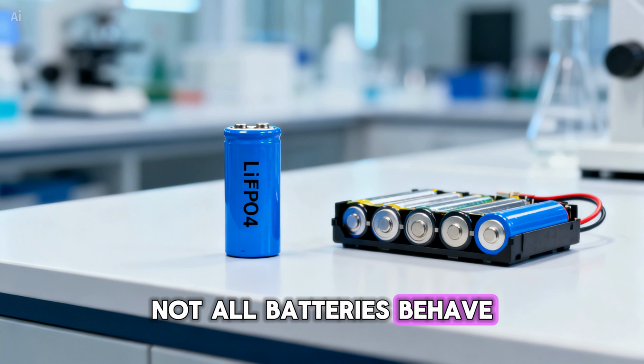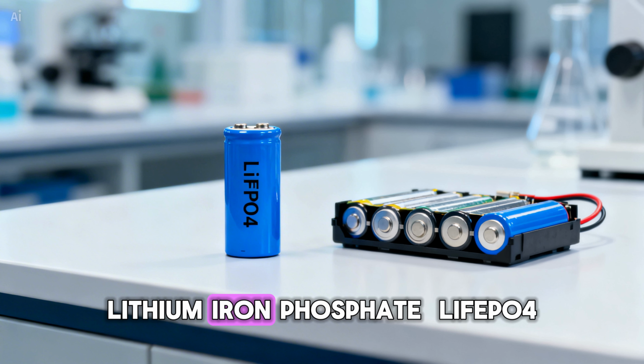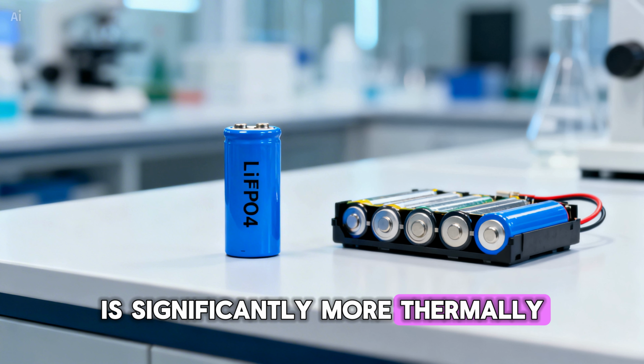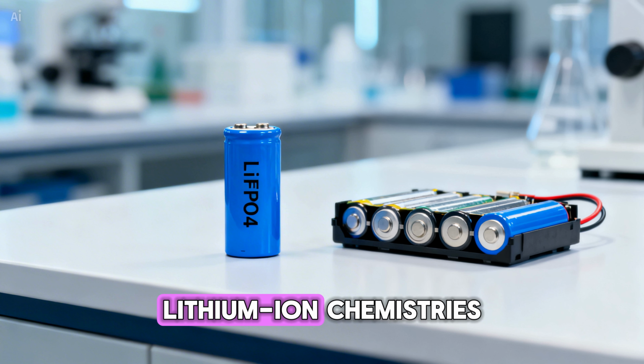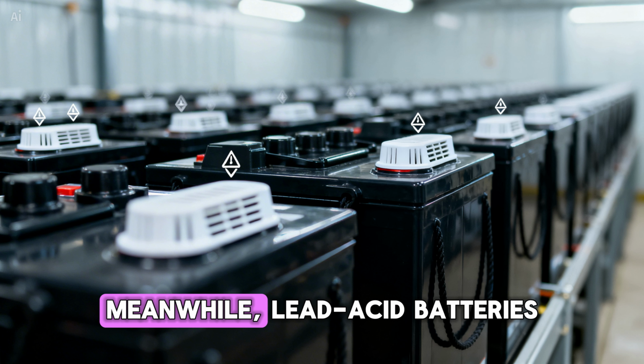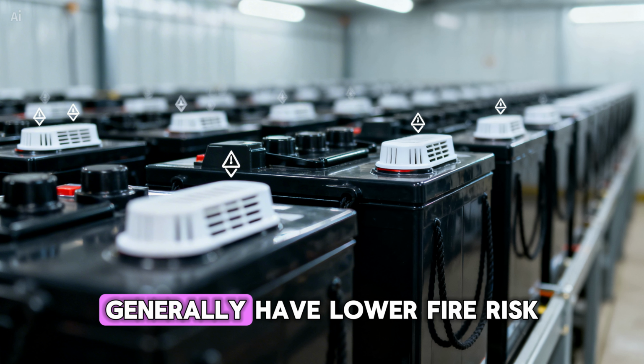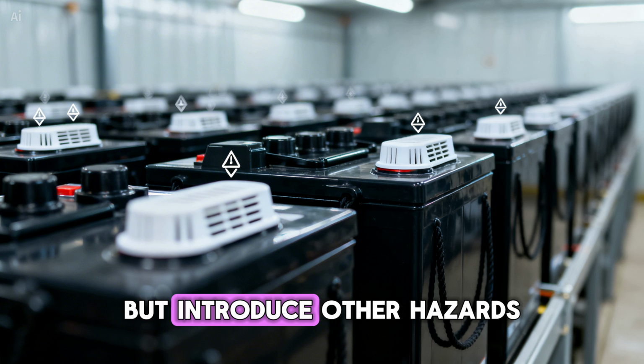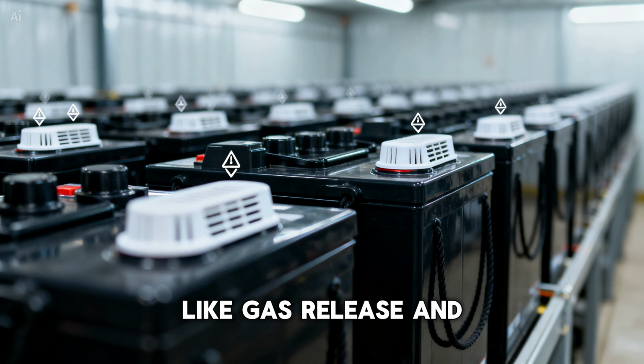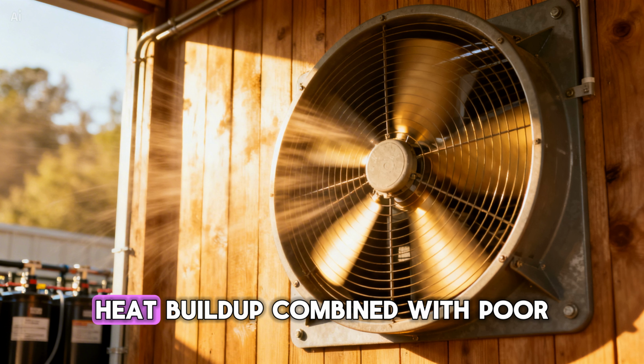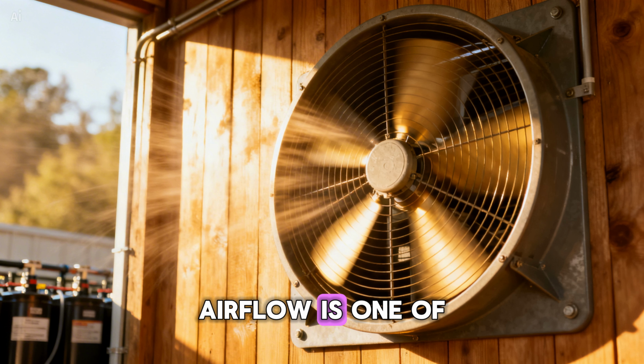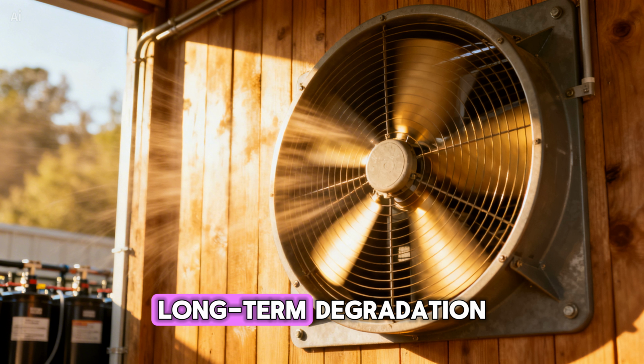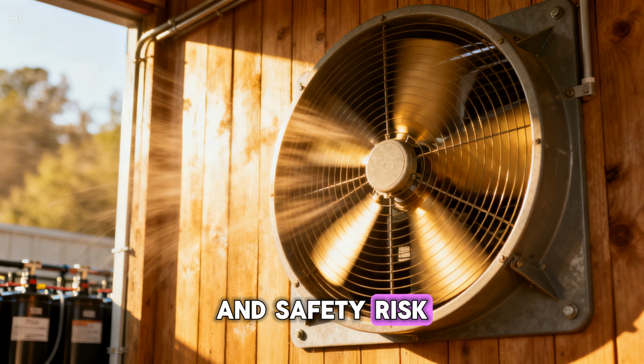Not all batteries behave the same. Lithium iron phosphate, LiFePO4, is significantly more thermally stable than older lithium-ion chemistries. Meanwhile, lead-acid batteries generally have lower fire risk but introduce other hazards like gas release and acid exposure. Heat buildup combined with poor airflow is one of the fastest paths to long-term degradation and safety risk.